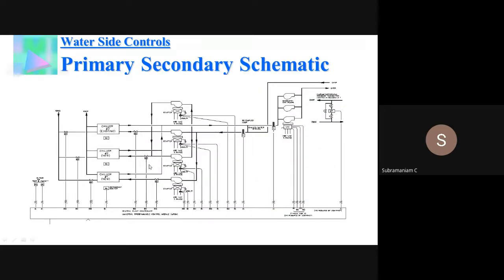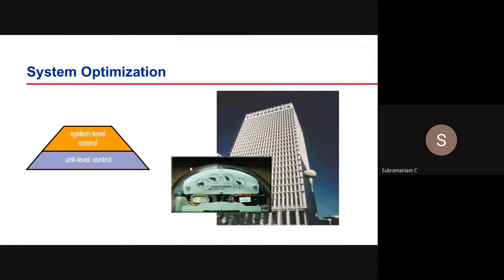Now this is something on how you build IO points for the water side, the chilled water side and pump chiller plant. So what you see here in this drawing is chillers. There are 3 chillers. There are primary pumps here, 1, 2, 3, 4. Then there are secondary pumps here. On the bottom, you see the DDC controller. You will find AI, BI, DI, AI, BI, BO, AO, like that. Similar to the logic we said before, we will have a motorized valve at the chiller output. For this, we have to follow that logic and build the controller based on my digital input, digital output, analog input, and analog output there.